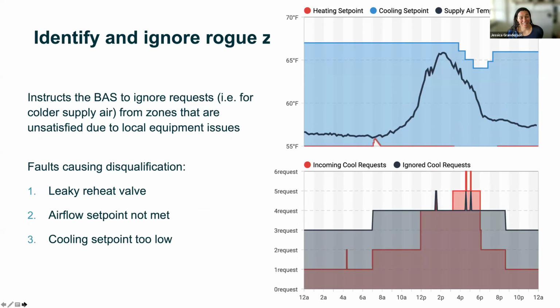A nice piece of this, since we've got the analytics in place, is identifying rogue zones and disqualifying their calls for cooling. That's this strategy in action—you could define it different ways. In this case, faults that would disqualify a zone included a leaky reheat valve, not meeting the airflow set point, or a cooling set point that was just too low and overly aggressive.